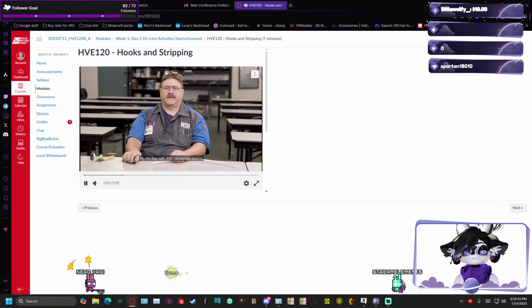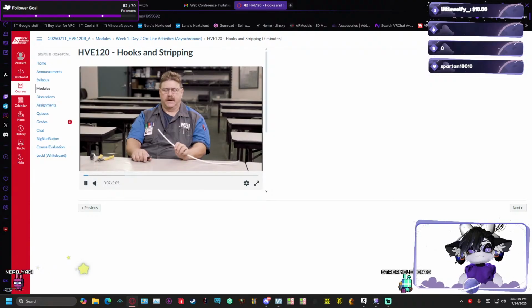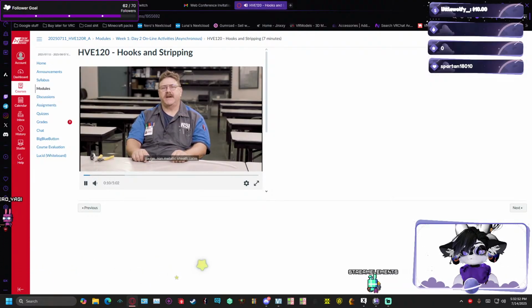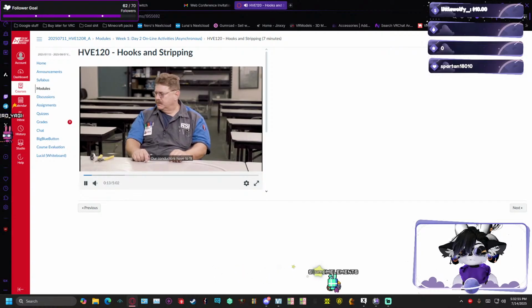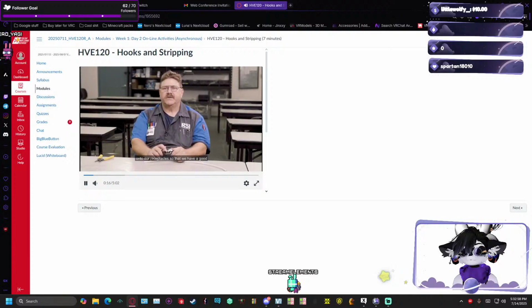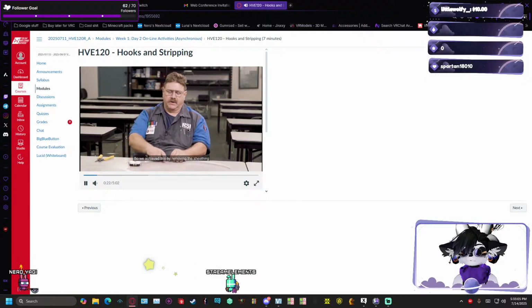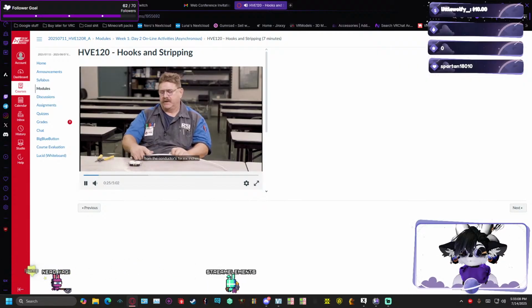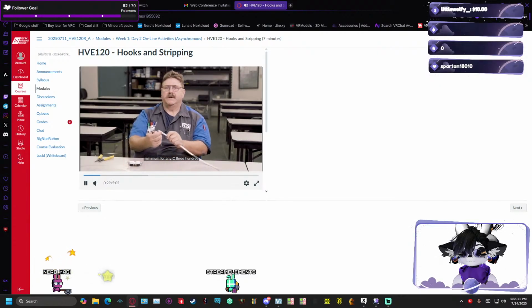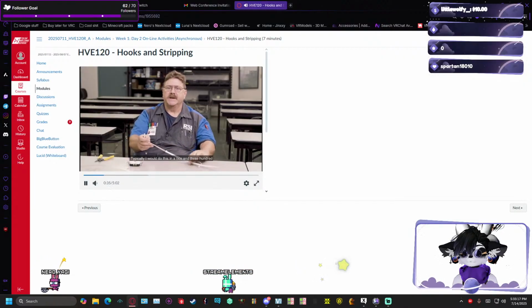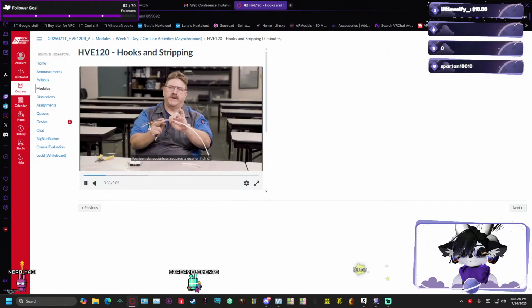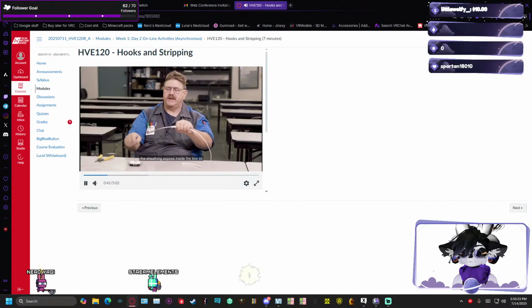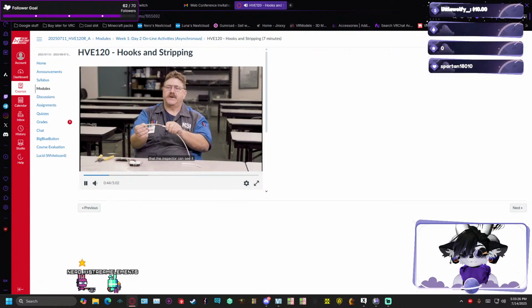Hi, I'm Ray with RSI Residential Electric Phase 2. We're going to talk about stripping and hooking today for 14 gauge non-metallic sheathed cable. Our conductors have to fit onto our receptacles so that we have a good electrical contact between the screw and the receptacle itself. We achieve this by removing the sheathing from the conductors for 6 inches minimum. NEC 300.14 requires 6 inches of free conductor in our box. Typically I would do this in a box, and 314.17 requires a quarter inch of the sheathing exposed inside the box so that the inspector can see it.